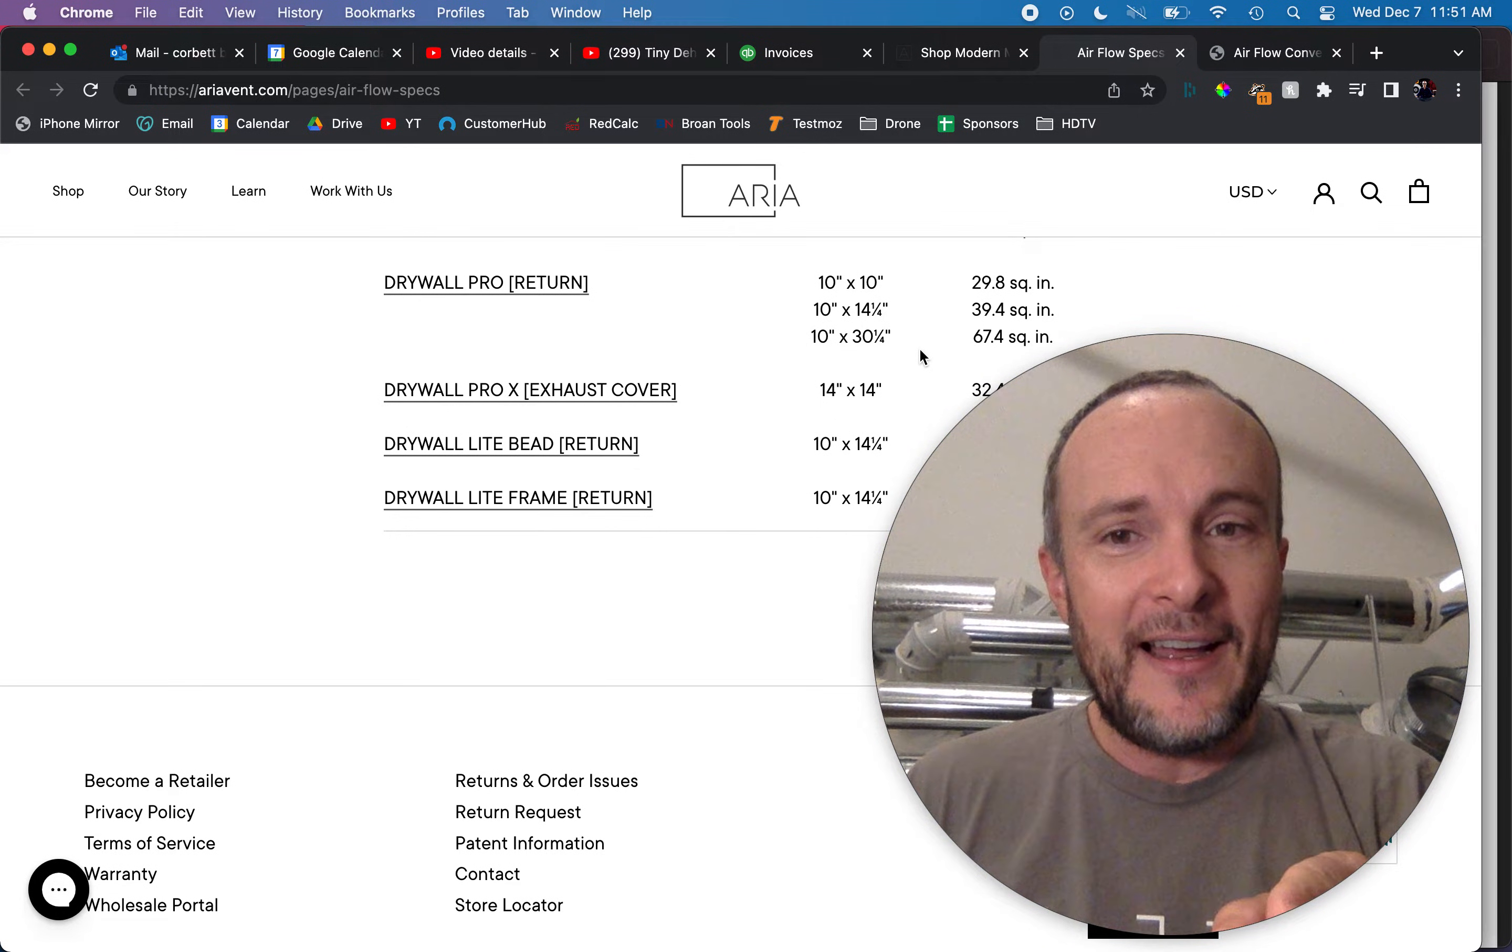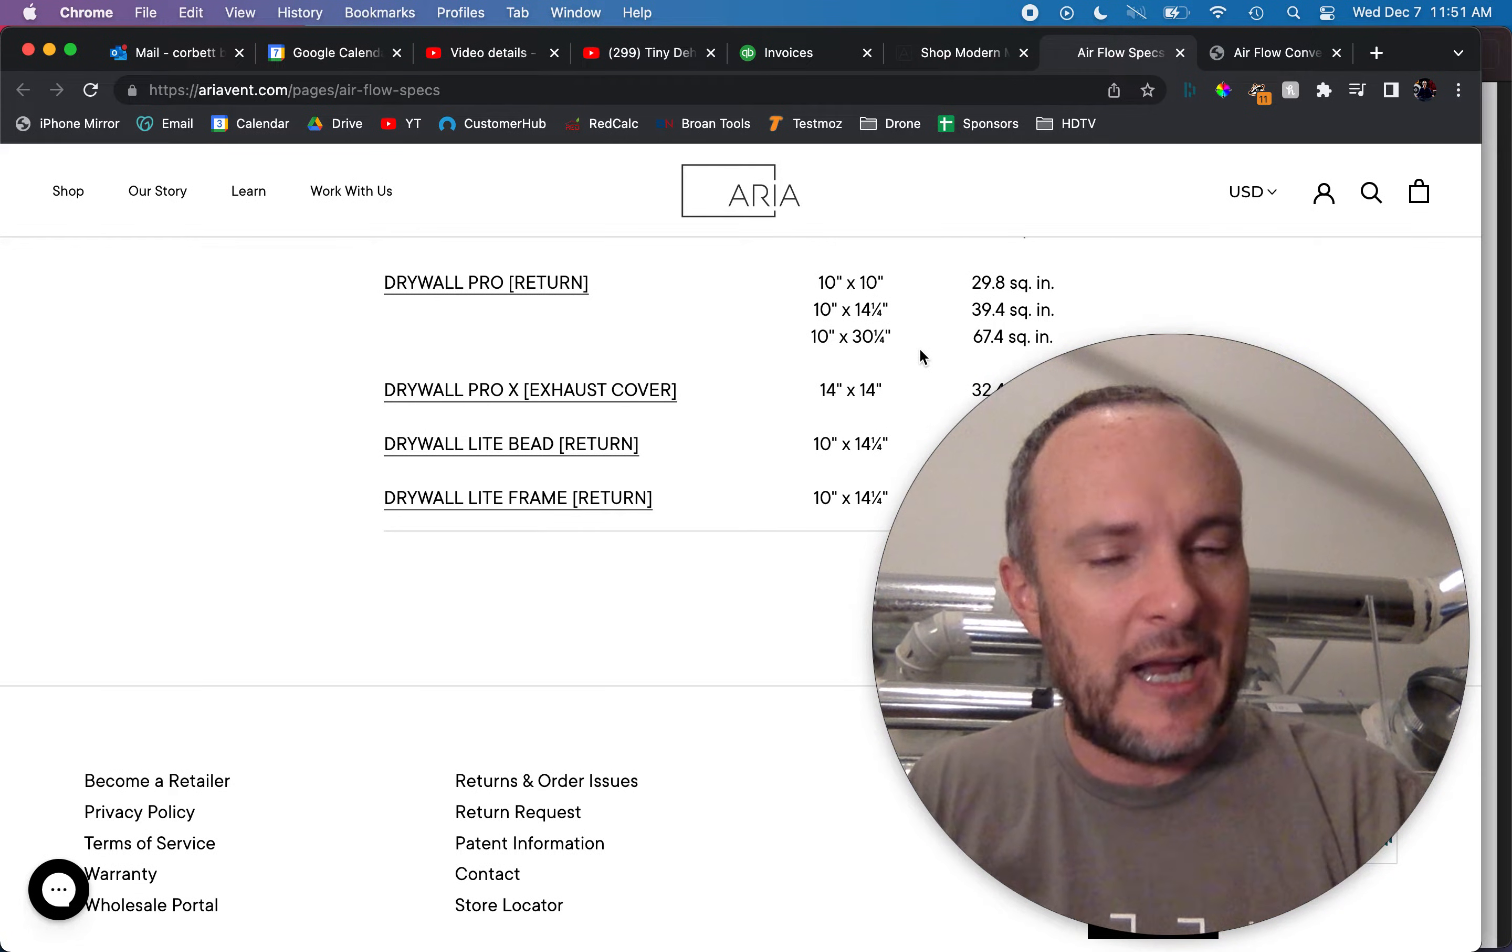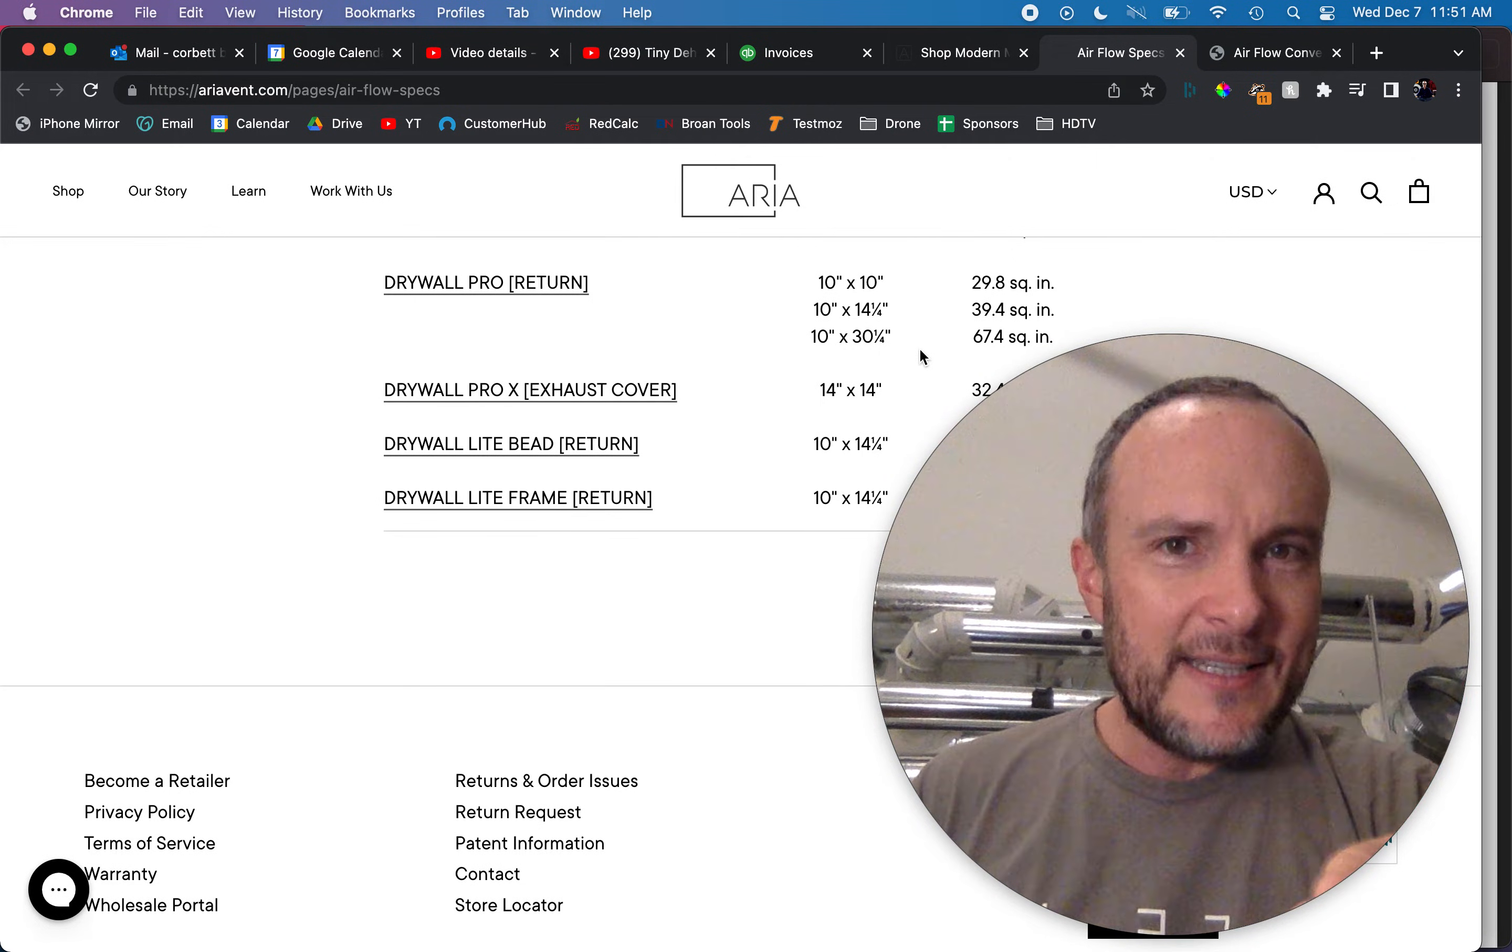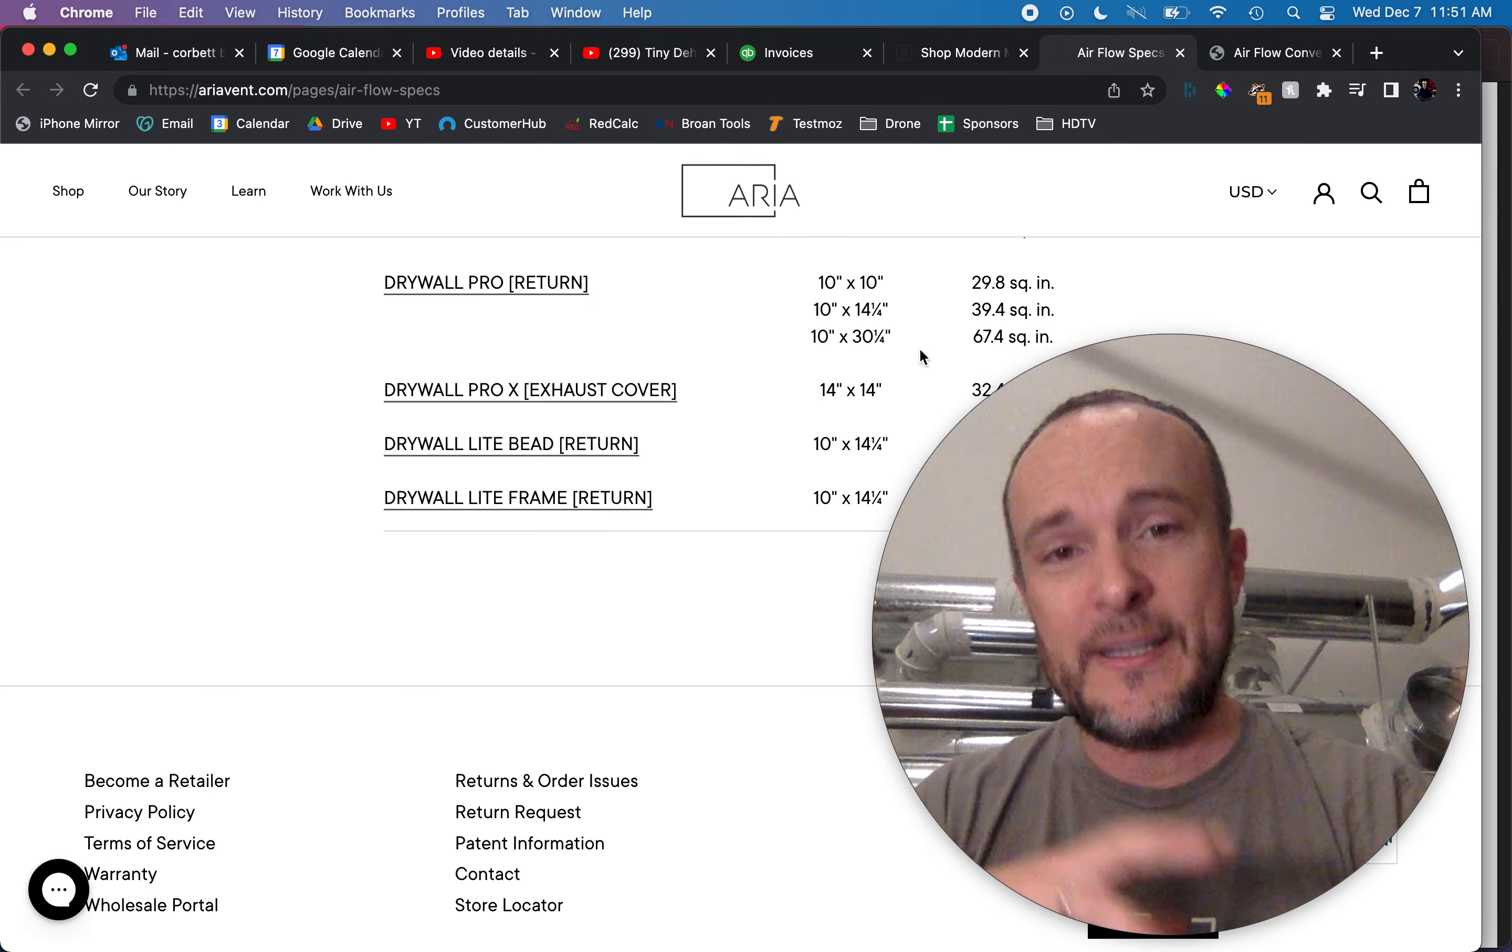This is normally you're looking at like 60% to 80% somewhere in that range for a metal grill. And the nice wood grills, like there's a company that I used on my own home called Aria Vents. You can see that video I'll link it on the screen here. But this is a very low net free area and essentially what we're trying to do is with a return you want the air velocity to be even lower than on a supply.